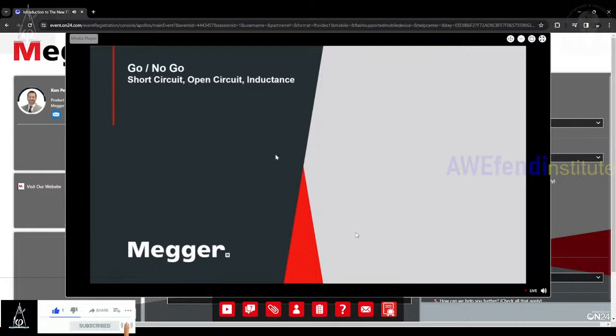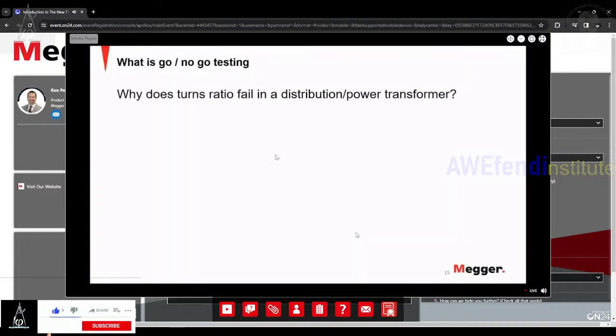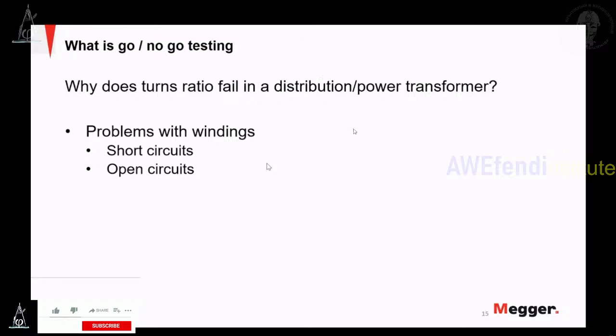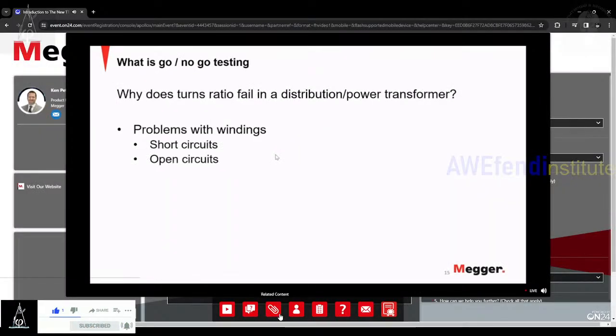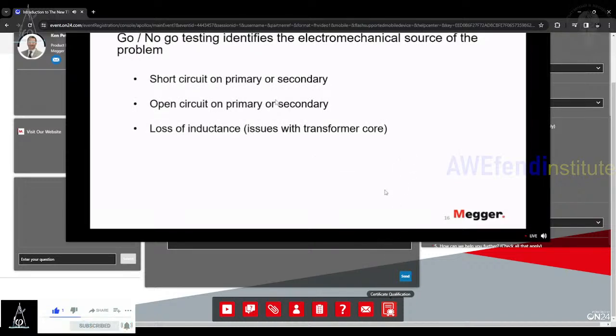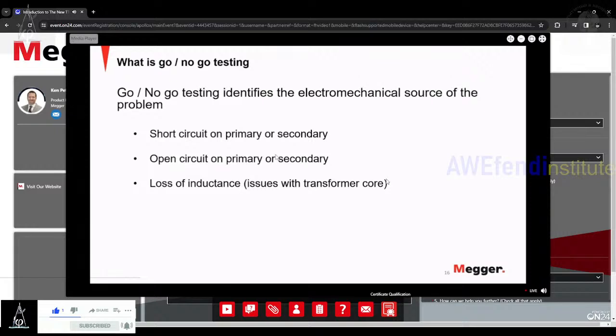The next test that we've added into the TTRU1 is the go, no go, short circuit, open circuit, and inductance test. So if you have a turns ratio test that fails, you're going to want to understand why it's failing. These are some typical problems that you may have: there's a short circuit in one of the windings, or there's an open circuit in another, or the transformer was subjected to an event and now it's got a problem with the core. This go, no go test, which is a different test mode on the TTRU1 Advanced and Pro, will give you this in-depth diagnostic of the transformer. And again, it's something that can go onto a report. It can be used to explain to either your boss or to your customers that not only did we find a problem, we know exactly what that problem is, and you can make that recommendation of the maintenance strategy for that particular asset.